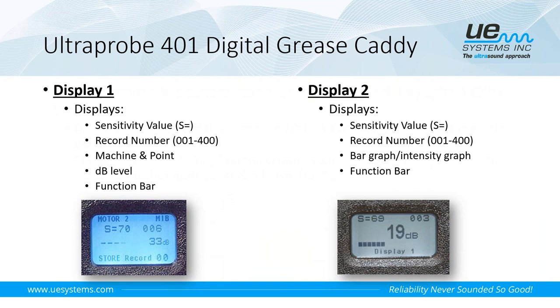All right, you do have two display settings. It's simply called display one, display two. In display one mode, you're going to see the sensitivity, the record number, the machine name, and the point name. You'll see the decibel level here in the middle, and then you'll see the function bar. More than likely, this will be the display of choice when you're using this.